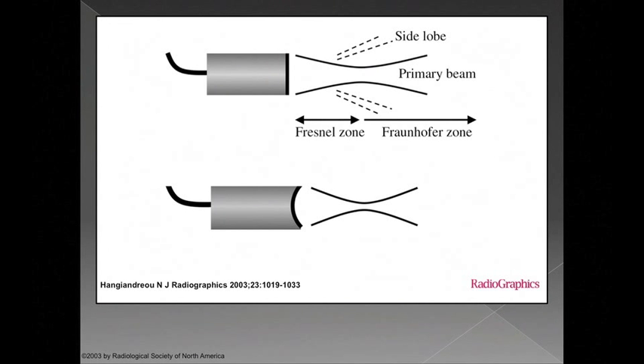The first thing that I want to talk about is how ultrasound beams are steered. Most of our modern transducers, whether they're linear transducers or sector transducers, use electronic interference to create a focal zone within the primary beam.